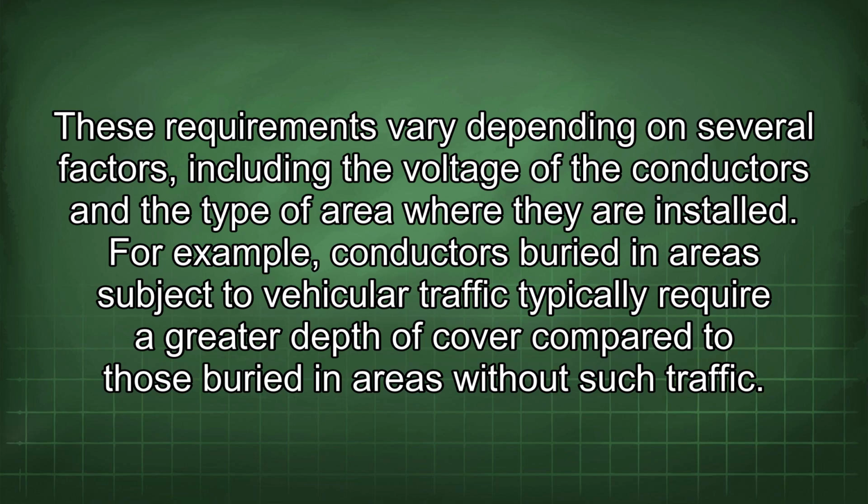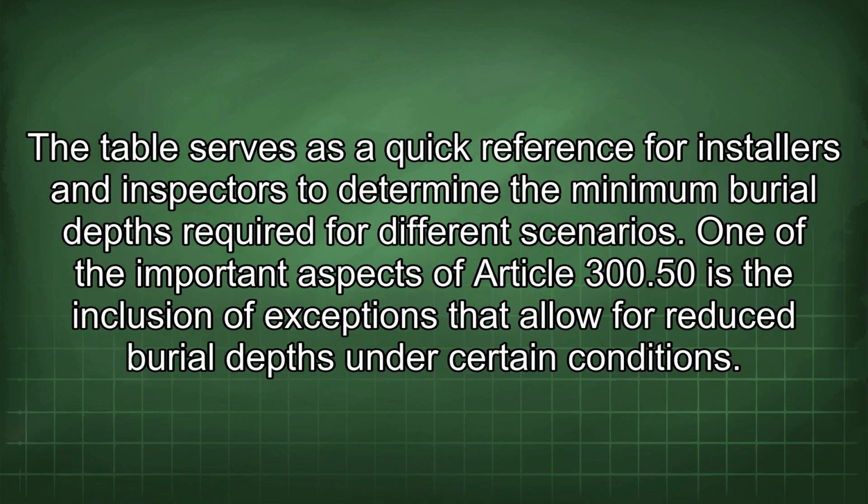For example, conductors buried in areas subject to vehicular traffic typically require a greater depth of cover compared to those buried in areas without such traffic. The table serves as a quick reference for installers and inspectors to determine the minimum burial depths required for different scenarios.